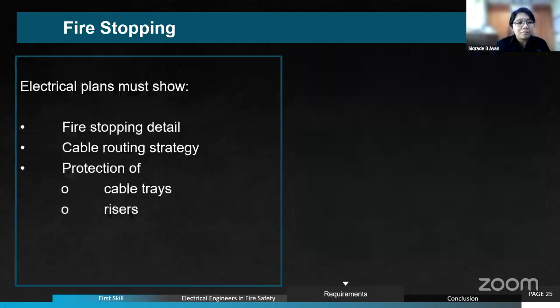So how do we check this during the design process? We should present the fire stopping detail in our electrical plans, our cable routing strategy, and what is presented in the protection of cable trays and risers. It's not just cable trays and risers we should look at—we should also check even simple things like utility boxes in our electrical plans. As much as possible, what we're trying to see in the electrical plans are the mitigation measures, the actions we can take to avoid these scenarios during fire, so that we don't end up with fire in our buildings.